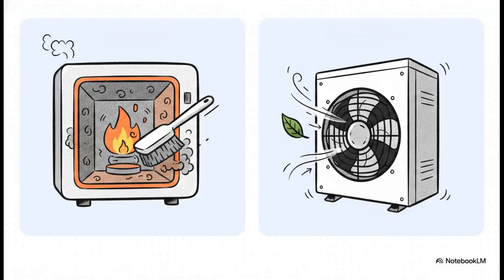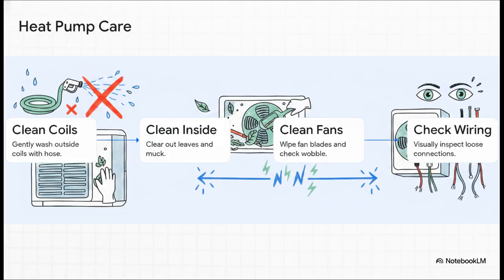To prevent long-term damage, we first have to realize that gas and electric heaters demand completely different care. I mean, gas heaters are essentially contained fires, right? So you're checking internal combustion elements like burner flames and clearing internal soot. Electric heat pumps, on the other hand, are all about the exterior. They work by pulling heat from the ambient air, so making sure the outside coils and fans can breathe easily is absolutely crucial.